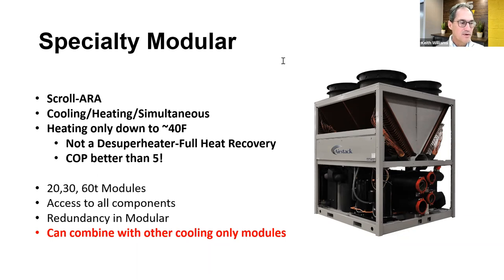I think you answered, we had a question about doing heat recovery on the refrigerants and on the systems. Is there anything special you want to add about heat recovery on refrigerant? Yeah, the ARA, the slide I got up on the screen, is a full heat recovery machine. It's not a de-superheater. There's not just a small braze plate capturing what it gets. It's forcing the machine to do 100% recovery. The heat that we've extracted out of the evaporator side, we add motor heat, and we dump all that heat into the condenser side heat exchanger, water on the other side, and that's how we convert this machine into a full water-to-water heat recovery chiller.